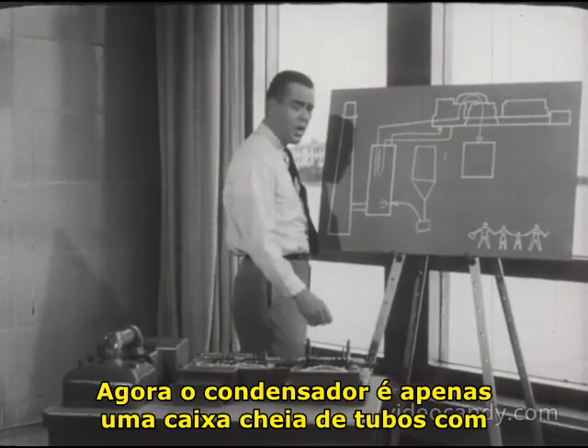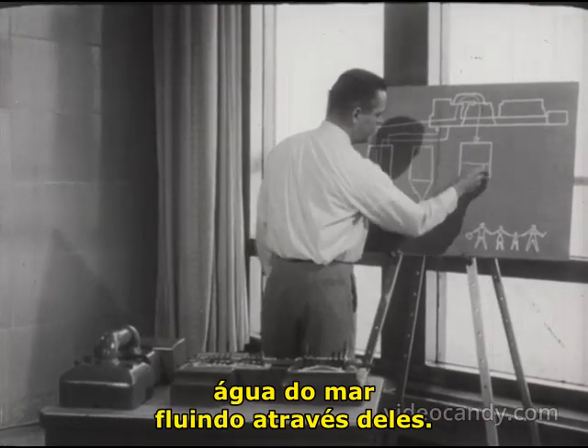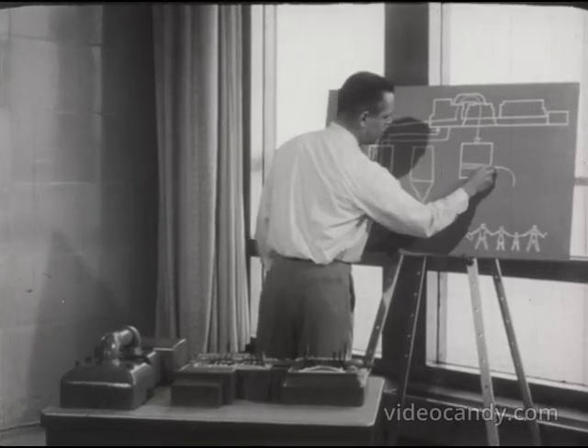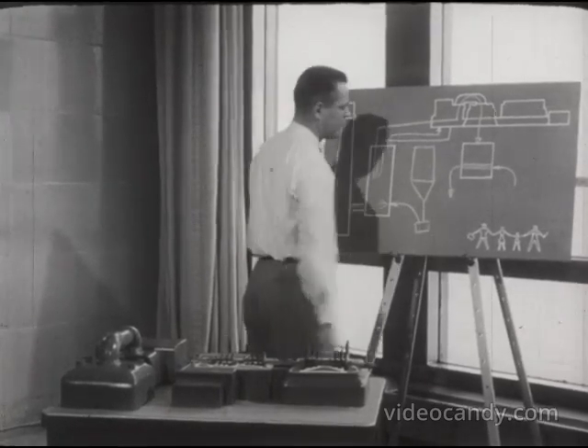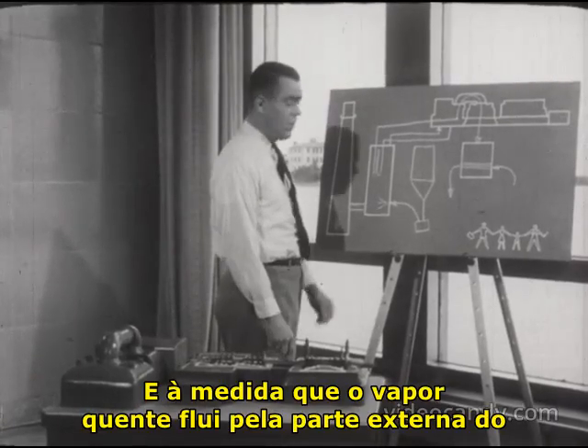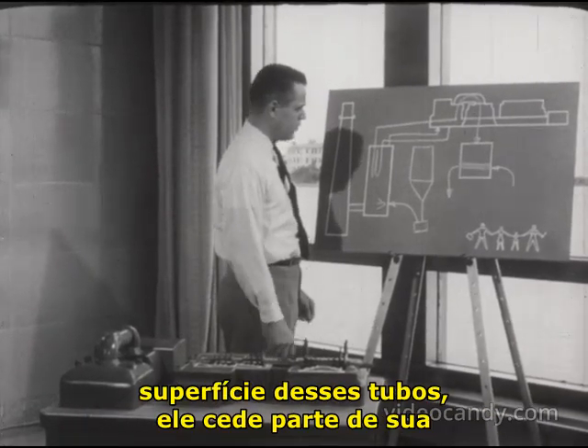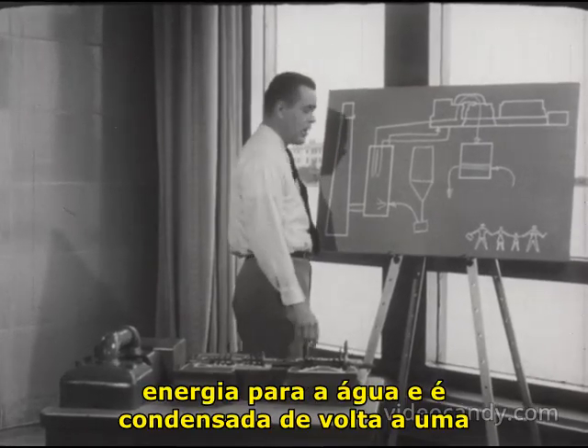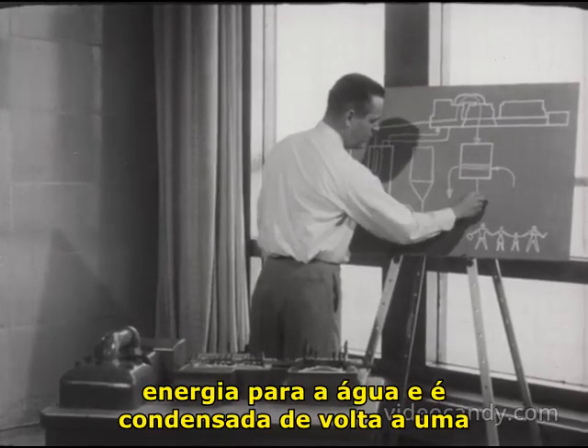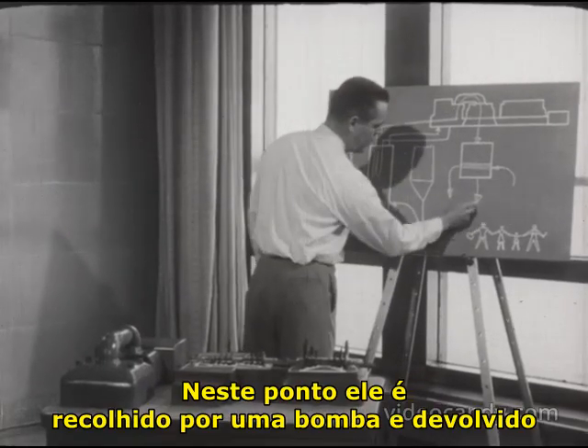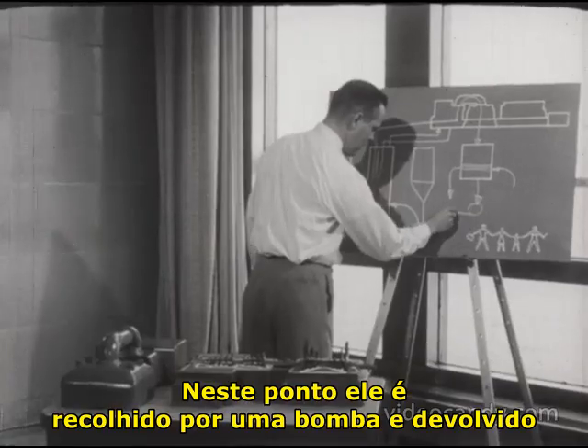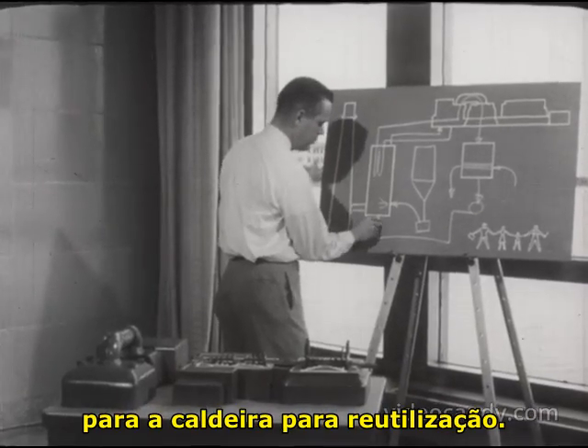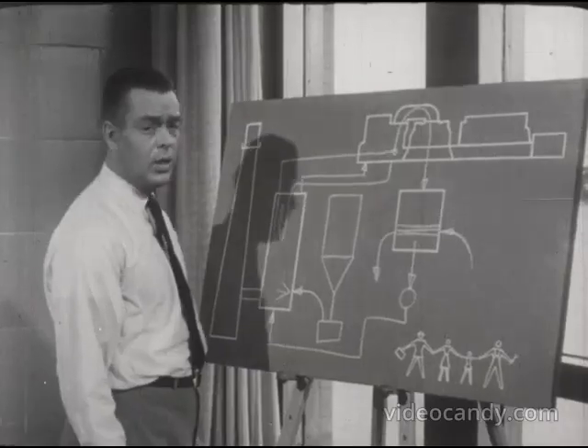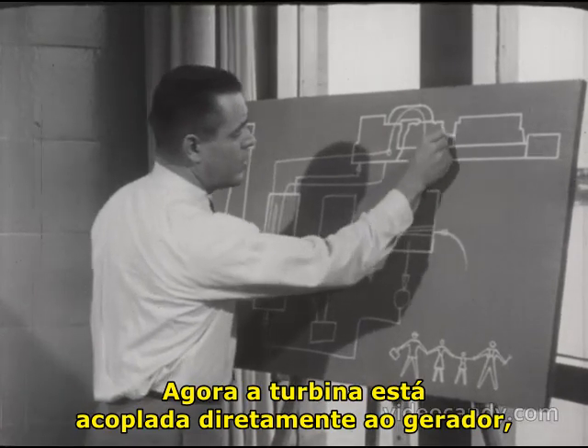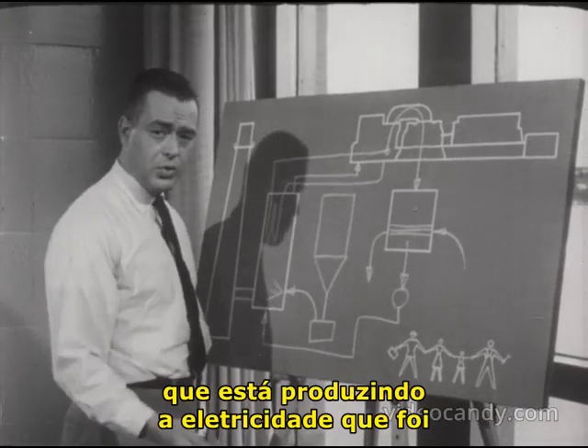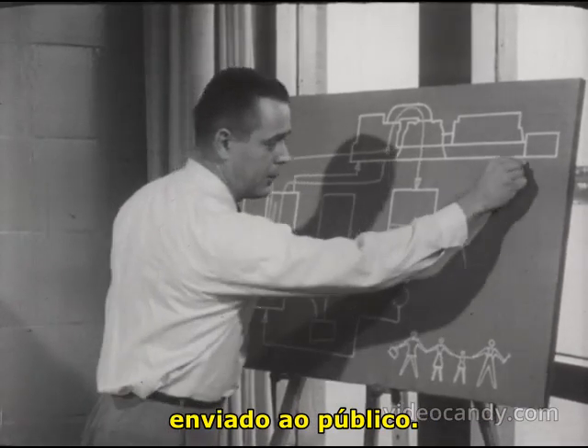Now, the condenser is just a box full of tubes with seawater flowing through them. And as the hot steam flows over the outside of the surface of the tubes, it gives up some of its energy to the water and is condensed back to a liquid form. At this point, it is picked up by a pump and returned to the boiler for reuse. Now, the turbine is coupled directly to the generator, which is producing the electricity which is being shipped to the public.